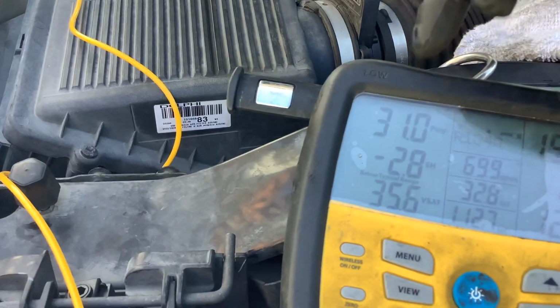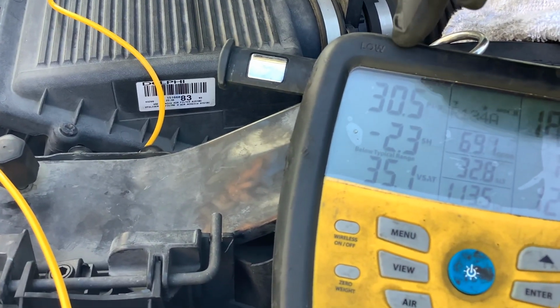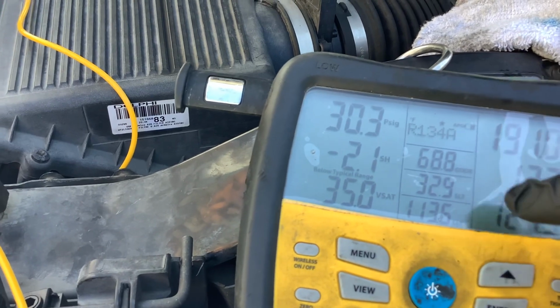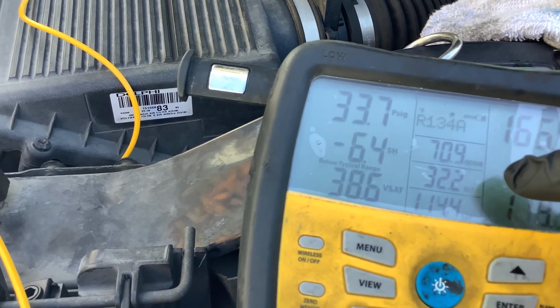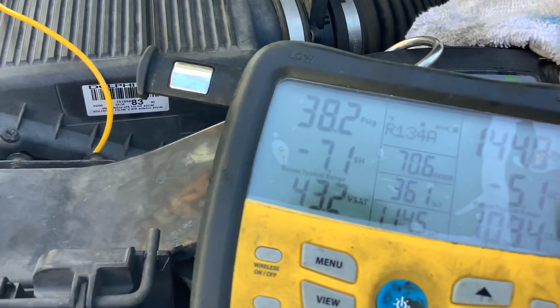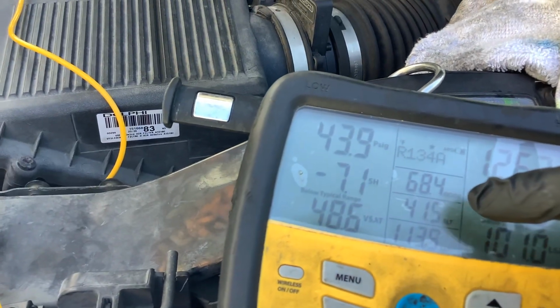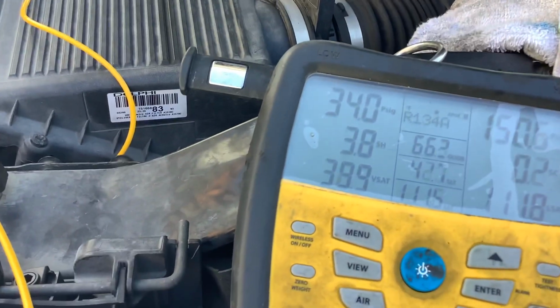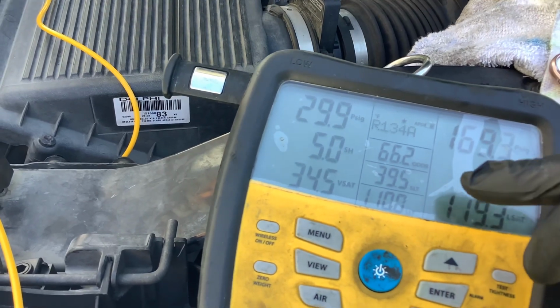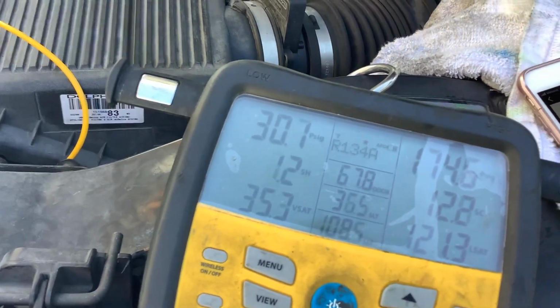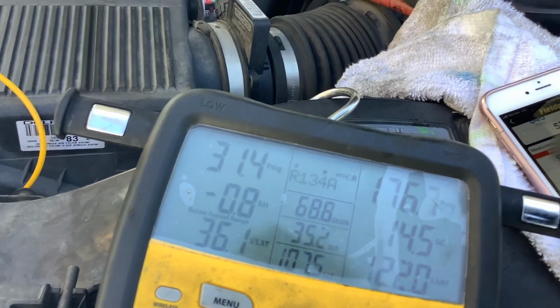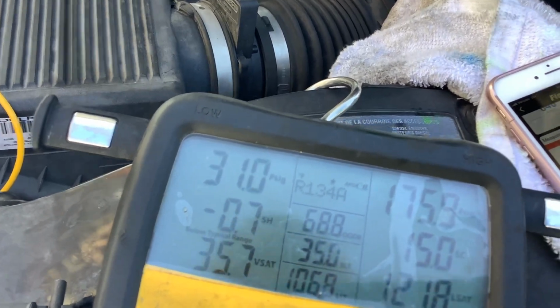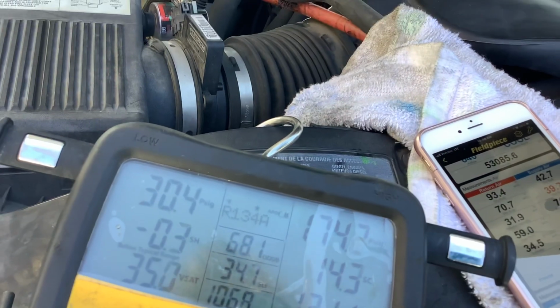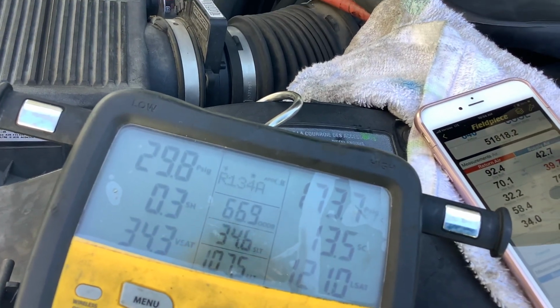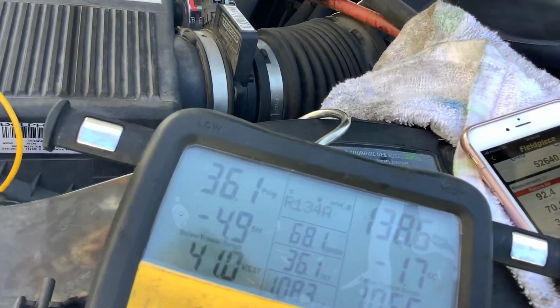We're down to 42 degrees. Let's look at the pressure. When we were 40 or 41 on the low side, we're dropping. Our suction line, we're down to 32 degrees. That's up. I think the compressor just kicked out. Yes. At 32 degrees, the compressor just kicked out. And that's 32 degrees measuring the suction line, not the duct air temperature. So when this hits 32, what is our air temperature? 34, and we're at 42. So it's right around in there.